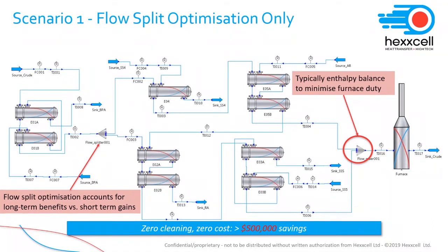For this reason, when we do our optimization of the flow split, we consider not only the enthalpy balance before the furnace, but also the impact of an adjustment in the flow split on the long-term fouling behavior. Thanks to the use of the digital twins and the predictive capabilities of the models, the optimization will take into account all the interactions in the network and provide the optimal long-term operation settings for the plant. In this case, we estimated potential savings by simply optimizing the flow split without any cleaning actions in the order of $500,000 for 4 years of operations.